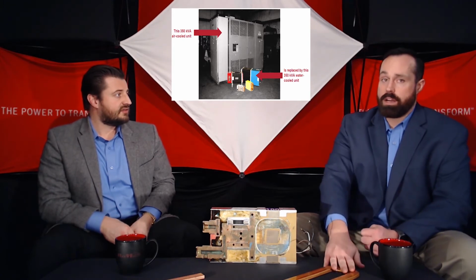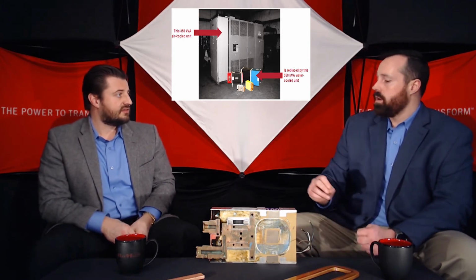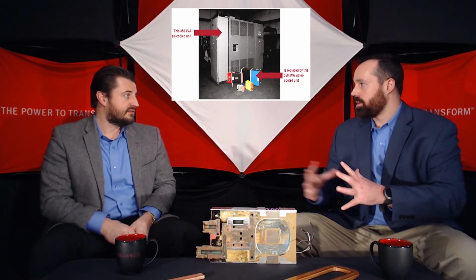Because of the heat-carrying capacity of water, we can make our transformers so much smaller. Interesting. So we've discussed this a little bit, but why don't you give us some of the bullet points on the real advantages of using a water-cooled transformer in your system versus, say, an air-cooled transformer?